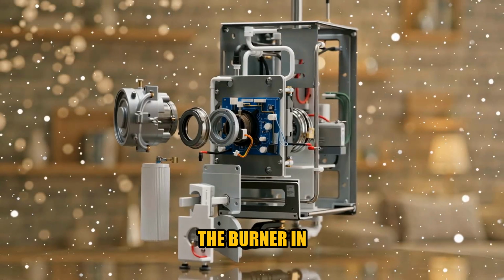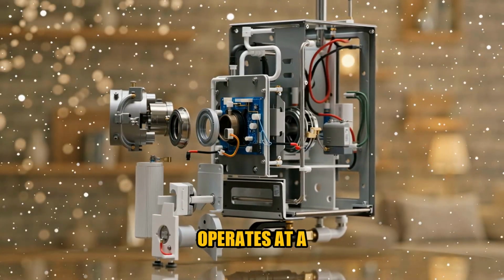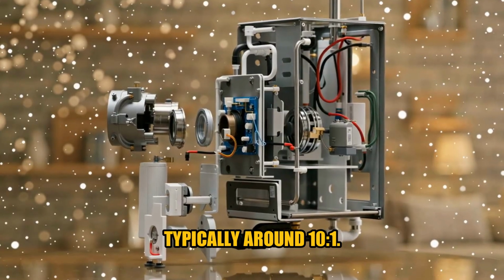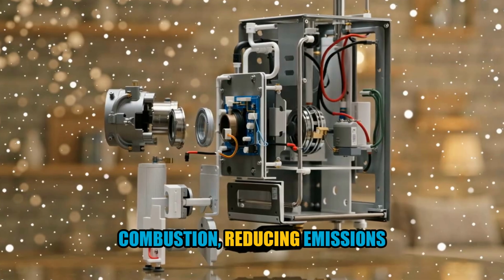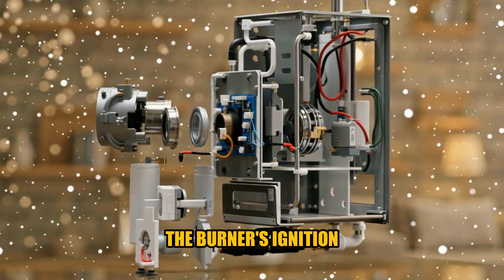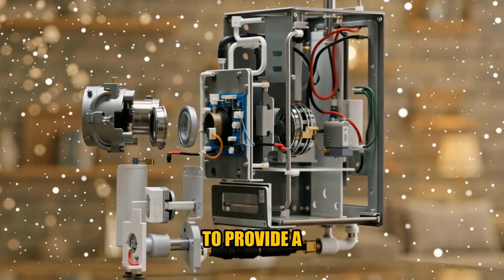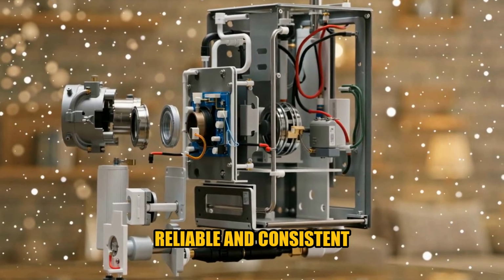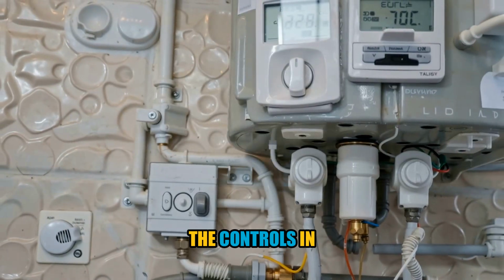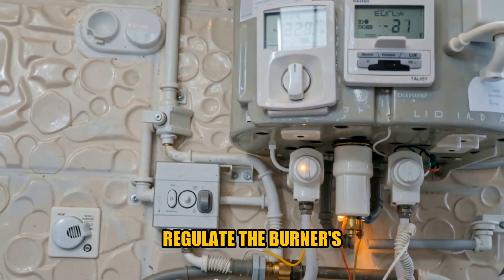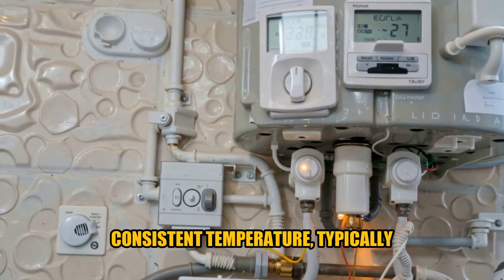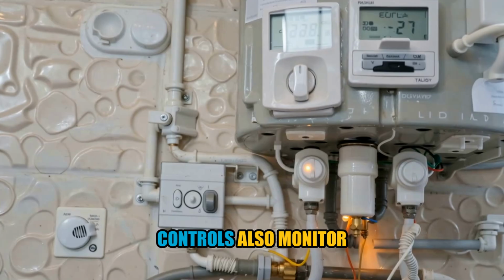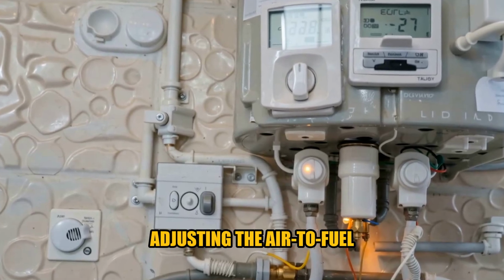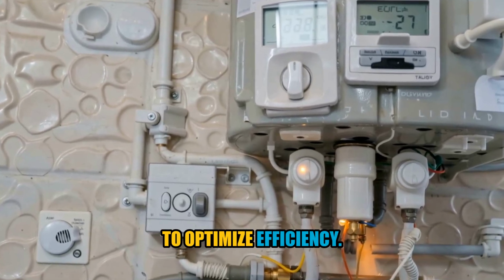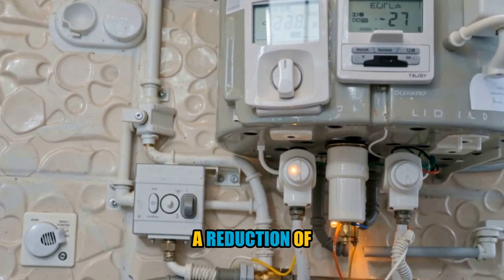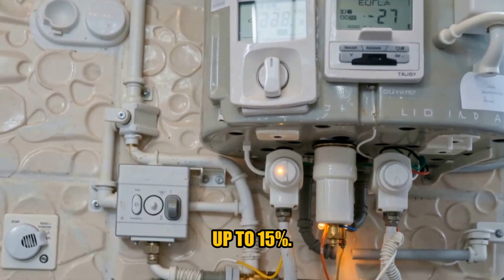The burner in a condensing boiler operates at a precise air-to-fuel ratio, typically around 10:1. This ensures complete combustion, reducing emissions and improving efficiency. The burner's ignition system is designed to provide a reliable and consistent flame. The controls in a condensing boiler regulate the burner's operation, maintaining a consistent temperature, typically around 80 °C. The controls also monitor the boiler's performance, adjusting the air-to-fuel ratio as needed to optimize efficiency. This results in a reduction of energy consumption by up to 15%.